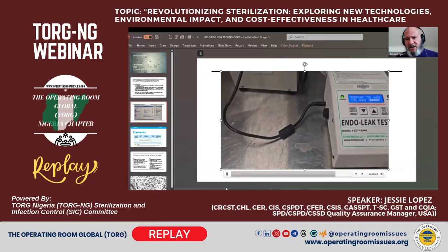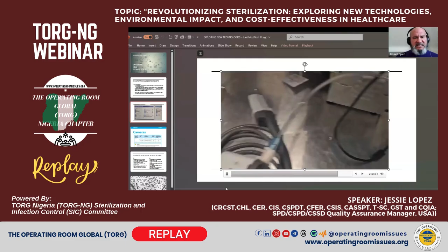So here I just turned on my unit. You can see that the pressure is being held at 150 plus or minus 3 or 4 millimeters of mercury of air. And we're going to observe the distal tip for 30 seconds. Okay. We're looking for slow streams of bubbles or fast streams of bubbles. That's going to show me that either this device is safe, there are no leaks, or there's a major leak and we need to put this device out for service. Okay. Everything is still connected.